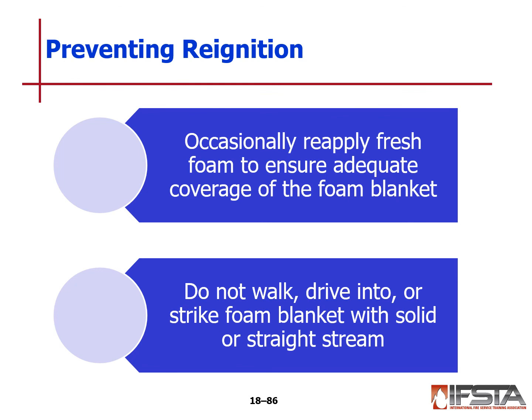To prevent reignition, occasionally reapply fresh foam to ensure that adequate coverage of the foam blanket is there. We don't want to walk through, drive into, or strike the foam blanket with solid streams or straight streams.